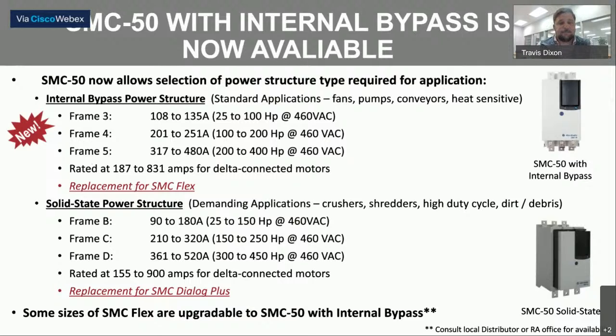For the solid state power structure, we can get it down from 90 amps on up to 520 amps for line connected motors, and from 155 amps to 900 amps for delta connected motors. And if you have any existing SMC Dialog Pluses out there, this is Rockwell's recommendation forward, is to go with the solid state SMC 50.